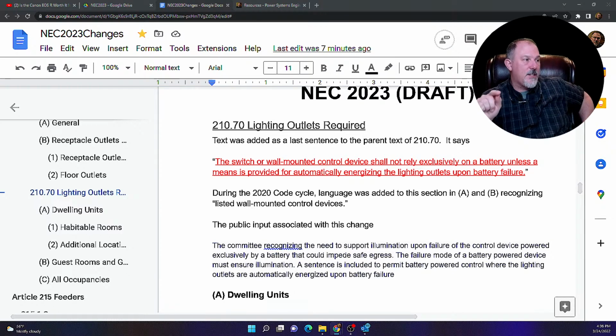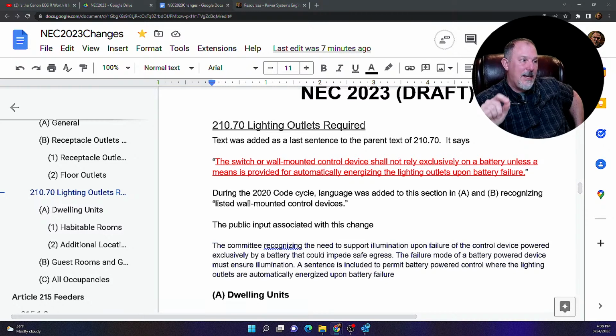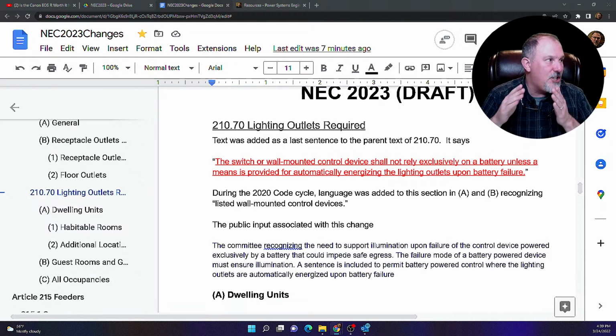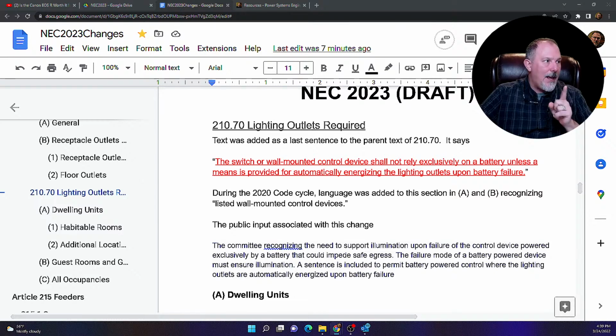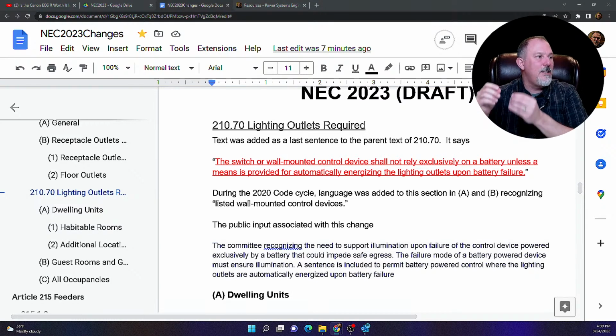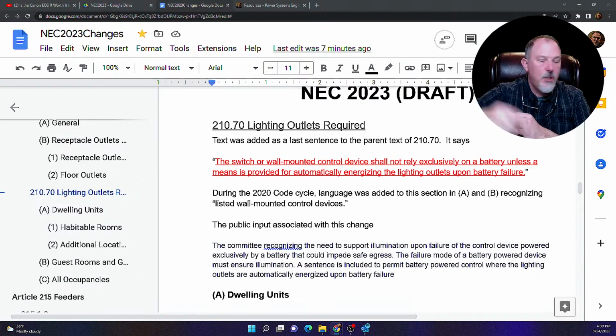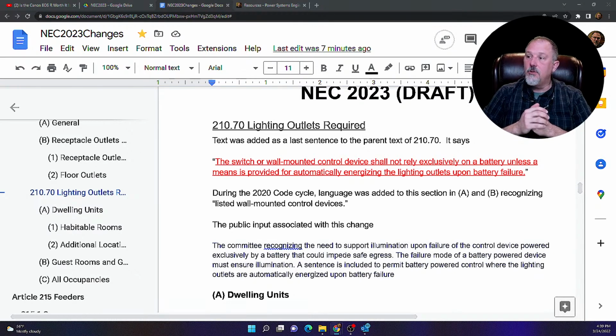The new text proposed for the driving language in section 210.70 corrects this issue. So what they suggested was to add text that switch-controlled lighting outlets covered in 210.70 shall be controlled by listed wall-mounted control devices that are electrically connected to the premises wiring system. Now, panel 2 obviously did not do that.